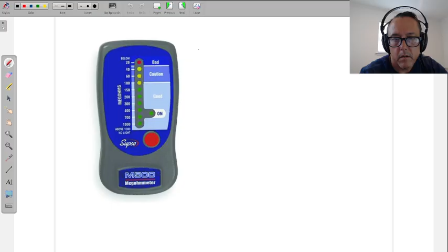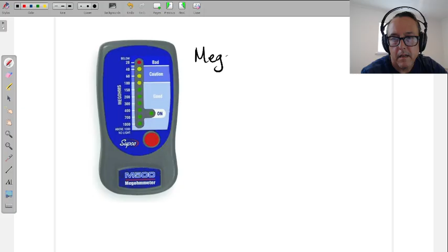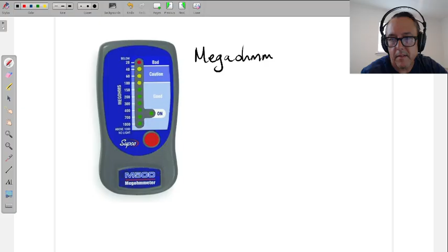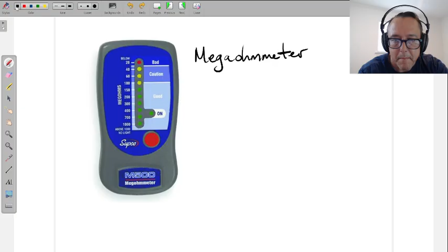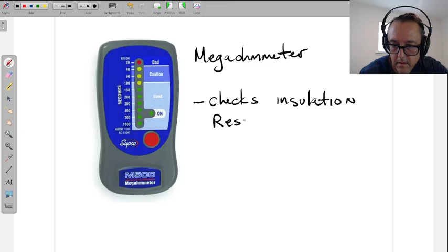This is the last one I want to give you the notes for. Mega ohm, one word, but the best name ever, right, because it's just three words. Megohm meter. Now the thing I want you to know is what it tests, it checks ohms, but not on the conductor, not on the copper side. This checks insulation resistance. What this tells you is whether the insulation around your conductor is good or starting to wear.